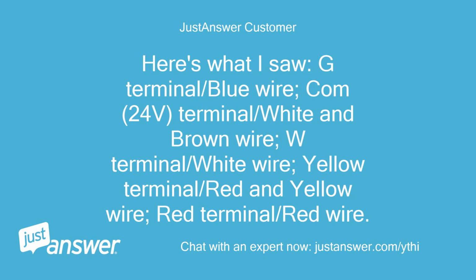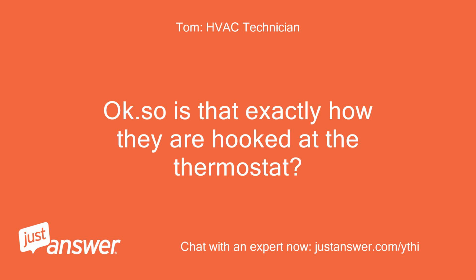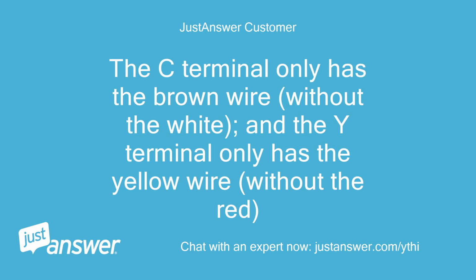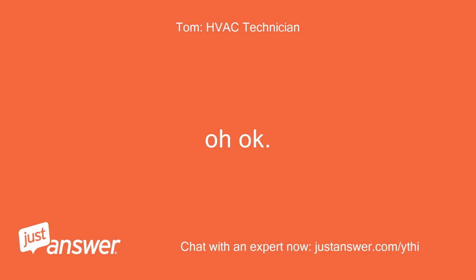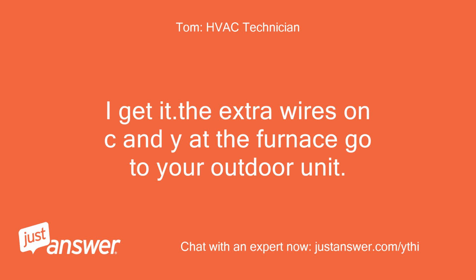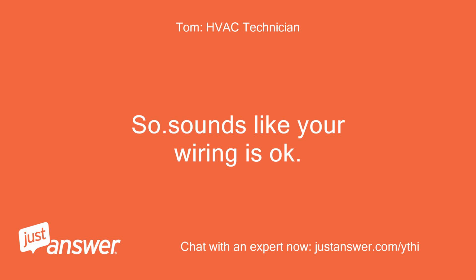Here's what I saw: G terminal / blue wire, COM 24 volts, terminal / white and brown wire, W terminal / white wire, yellow terminal / red and yellow wire, red terminal / red wire. Okay. So is that exactly how they are hooked at the thermostat? The C terminal only has the brown wire, without the white, and the Y terminal only has the yellow wire, without the red. Oh, okay. I get it. The extra wires on C and Y at the furnace go to your outdoor unit. So sounds like your wiring is okay.